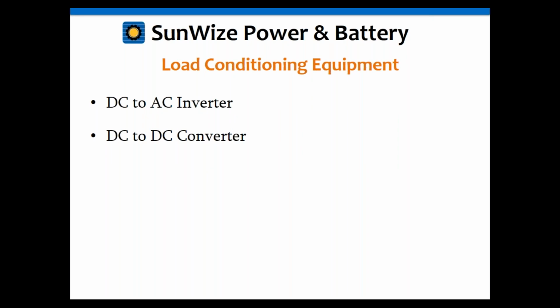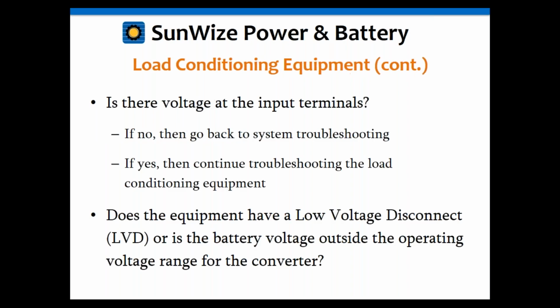Okay, and lastly, let's get into load conditioning equipment. This is another one where I've had calls where the charge controller has gone bad or the system has failed, and as it turns out, it's the inverter or converter that's the problem. So we're going to go into that briefly. Just to give you an overview, you may need to contact the manufacturers for more detailed troubleshooting. But let's get into some of the basic things you can look for and some of the simple things you can do.